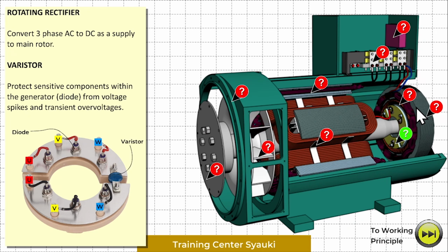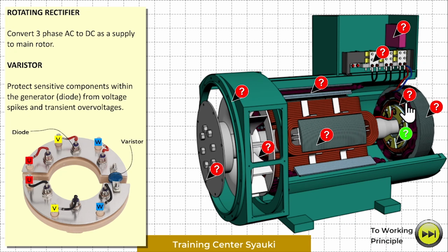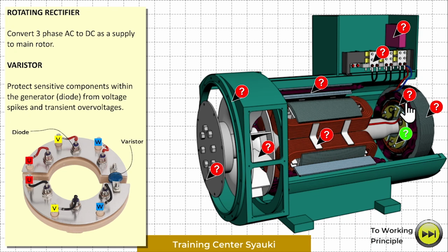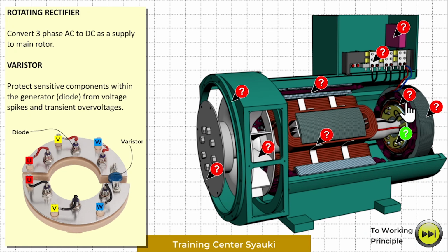The rotating rectifier in a brushless generator serves the crucial function of converting the alternating current generated in the exciter rotor into direct current for the generator's excitation system. This conversion is necessary for creating a stable magnetic field in the generator's main rotor to induce the required voltage in the stator winding.